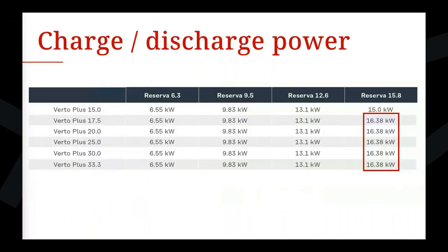This table shows you the max charge and discharge rates with the different Reserva and Verto Plus combinations. So your highest charge and discharge rate is going to be 16.38 kilowatts that you can basically get on any of the Verto Plus power classes, apart from the Verto Plus 15 kilowatt power class. There you get 15 kilowatts, which is pretty good though, considering that you can get the full output of the inverter. So there's a lot more that we can talk about on the Verto Plus, but I'll leave it there for now. I just want to give you a little tidbit there just before it hits our shores.